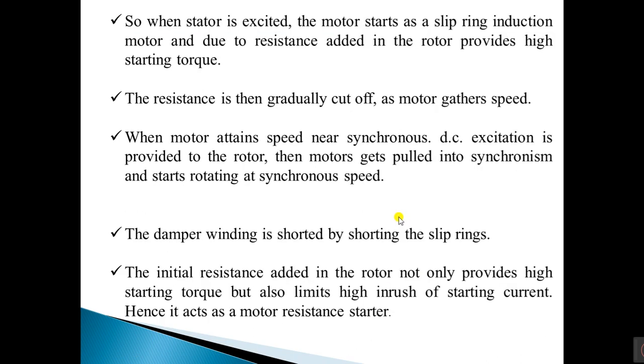So when the stator is excited, the motor starts as a slip ring induction motor, and due to the resistance added in the rotor, it provides high starting torque. The resistance is gradually cut off as the motor gathers its synchronous speed. When the motor attains speed near to synchronous, DC excitation is provided to the rotor. Then the motor gets pulled into synchronism and starts rotating at synchronous speed.